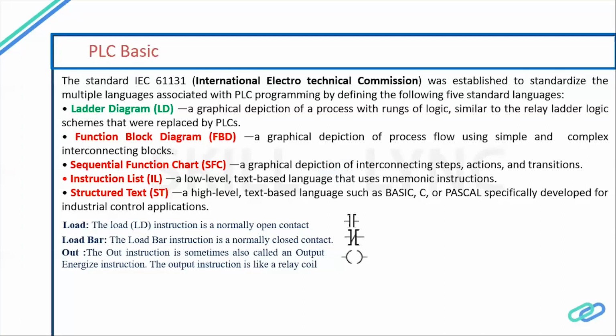Others are function block logic, sequential function chart, instruction list, or structured text. So there are different types of programming logic. In the present scenario, everybody uses function block diagram, FBD, or ladder logic. Nobody uses SFC, IL or ST, because ST is like C or similar languages, which is very typical and not easily understood. Function block and ladder logic do not require expertise in basic C or Pascal or any other language.